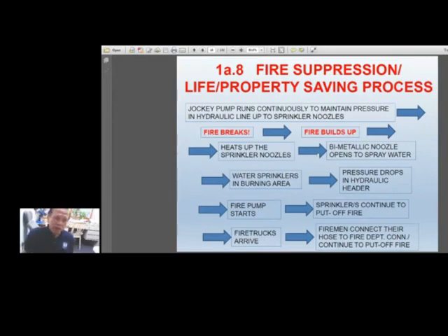Okay, so the first slide is more about saving the people, the occupants of the building, while the second slide is more about saving the property, because the water in the sprinklers cannot save a person. If a person is still inside the building, chances are he will get suffocated, or he will be inhaling toxic gas like carbon monoxide and others, and that will kill him. So it is the fire detection and alarm system that is life-saving, and the sprinkler system is more property saving, no? To prevent the fire from spreading, and of course from weakening the building.